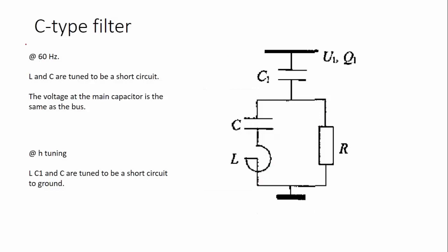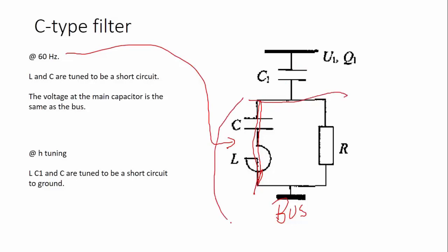So this filter works like this. At the fundamental frequency, which here in Mexico is 60 Hertz, maybe if you're in Europe, it's 50 Hertz, L and C, which are this branch, is tuned to be a short circuit. So at 60 Hertz, this branch is a short circuit. And then the only thing that you have, this is the main bus, is a short circuit from these two, and the main power capacitor. So the voltage in this bus is exactly the same as the voltage in this bus. And then you have the resistance.